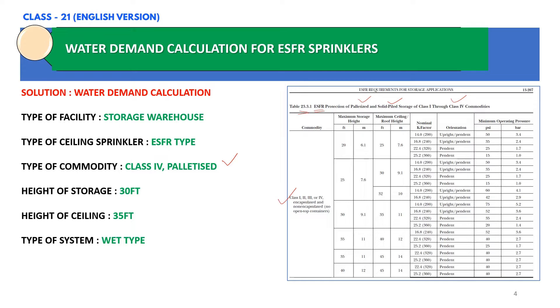In our case, the height of storage is 30 feet, so from the table we select maximum storage height of 30 feet. The height of ceiling is 35 feet, so maximum ceiling height is 35 feet. From here we need to select the nominal K factor of the sprinkler. Generally we go with K factor 14, but other K factors such as 16.8 can be considered — each will result in a different minimum operating pressure.